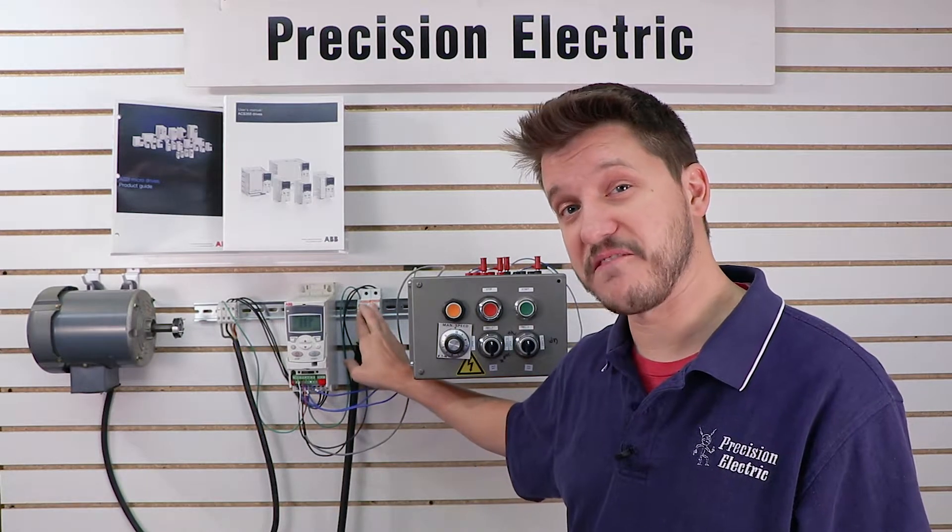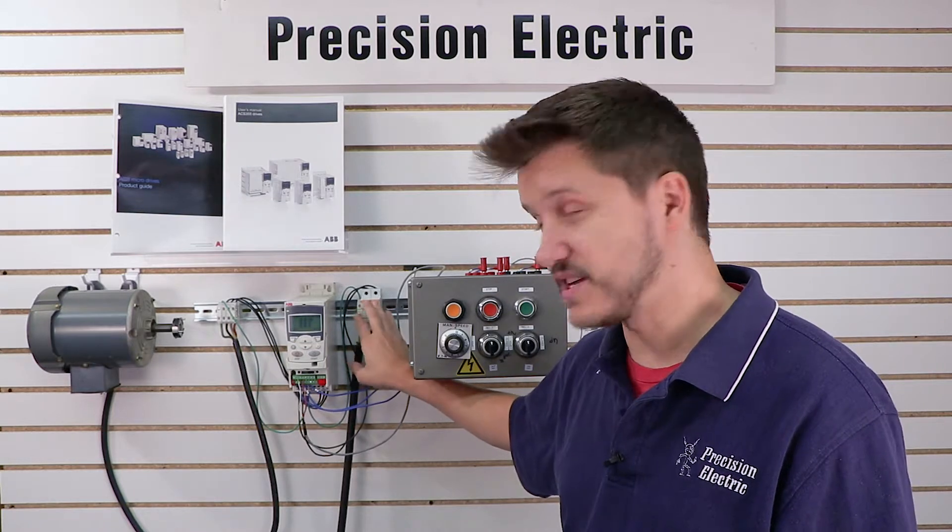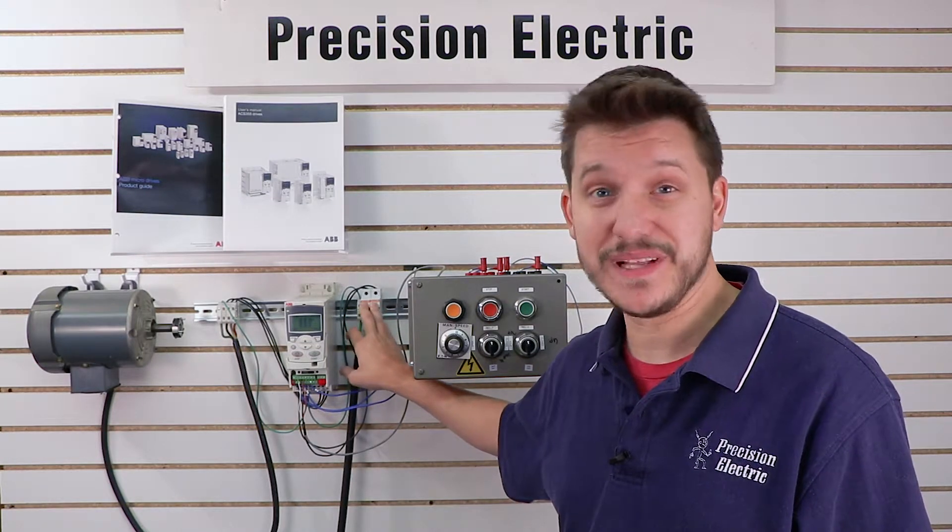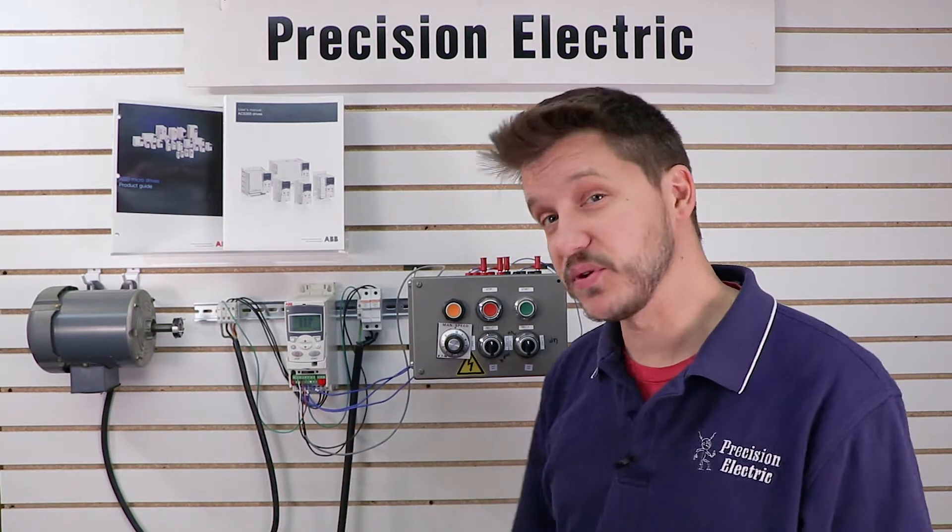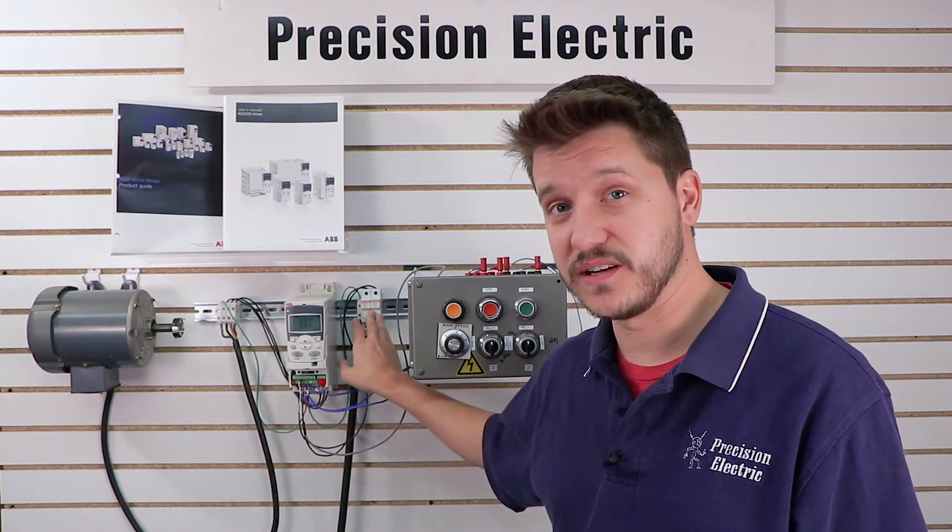The type of fuses we recommend, they're a little more expensive, are fast-acting current limiting fuses. And essentially, those are designed to blow within milliseconds of exceeding the rated current. A lot of people don't realize that. They don't take that extra step to get the fast-acting current limiting.